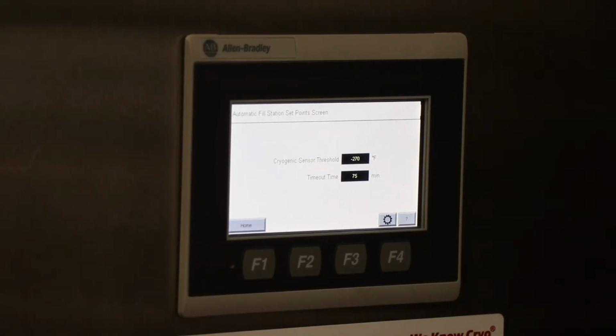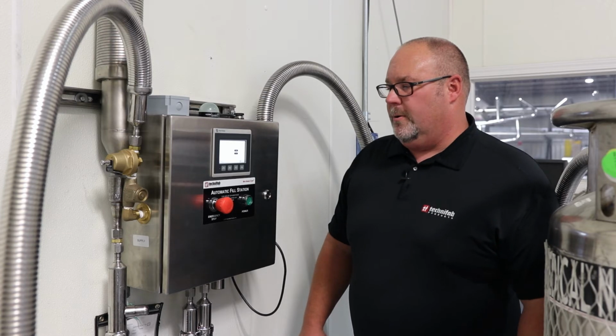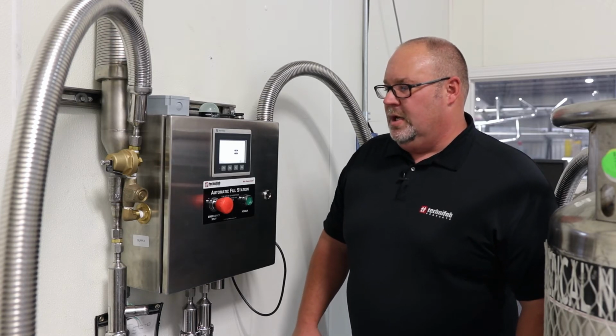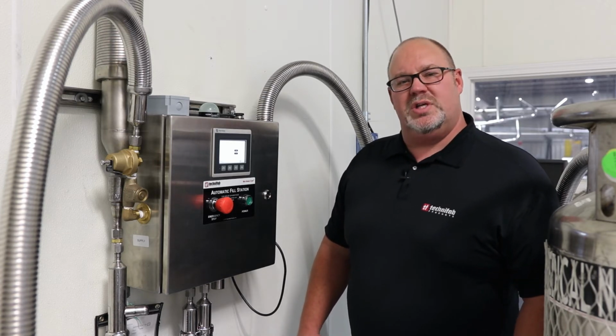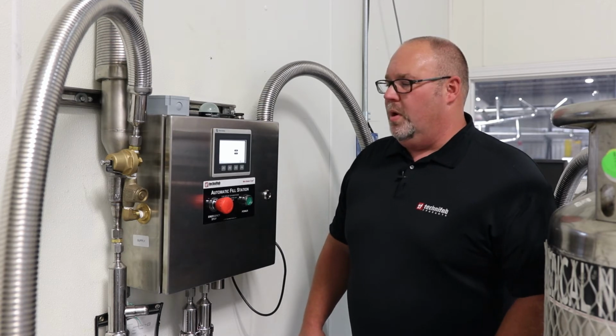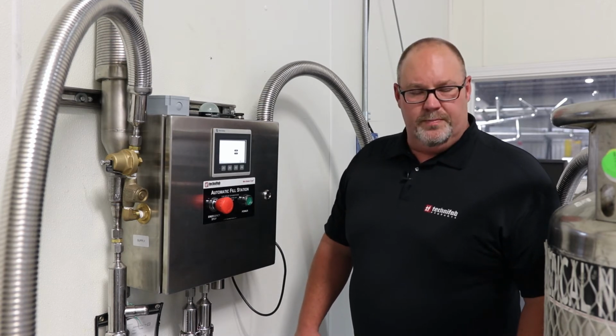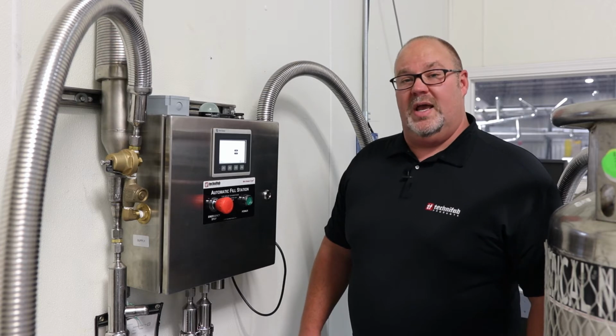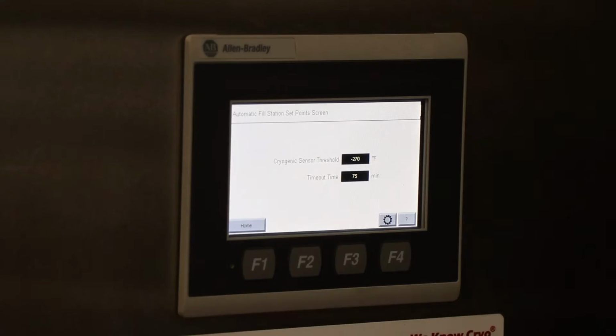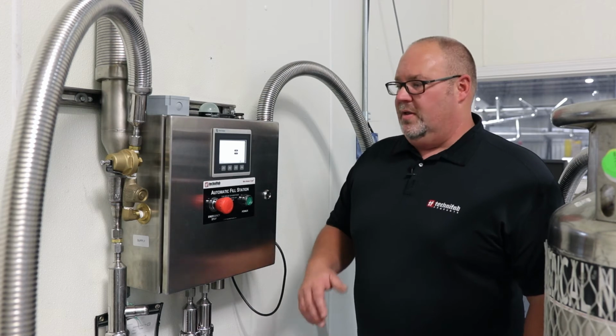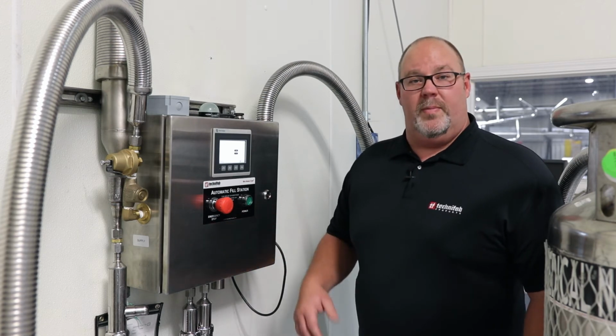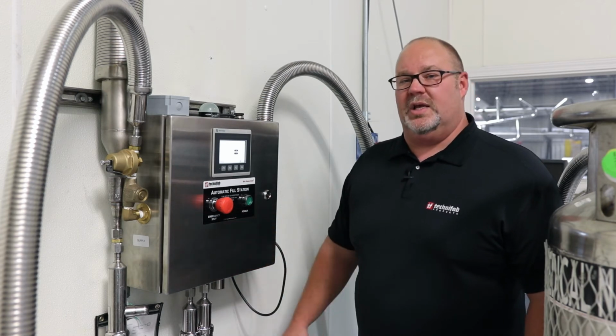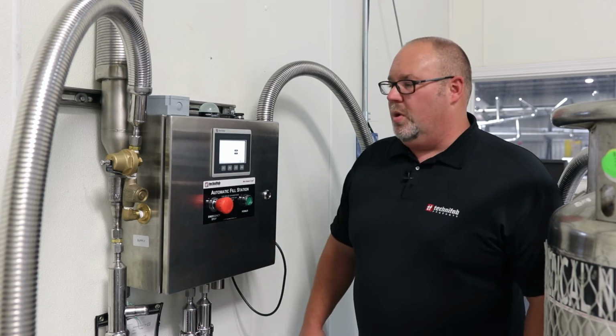Now that we're in the set points, there's two major set points that are available to be adjusted. That's your cryogenic sensor temperature threshold. The other one is your timeout timer. Both of these are preset at Technifab. The first one is currently set at minus 270 degrees, which is the temperature of your liquid. If you're starting to see warmer temperatures, which is what you would see in a gas phase, then that would give a notice that says, hey, we may be done filling, or we may have a supply tank issue, depending on what's going on there.